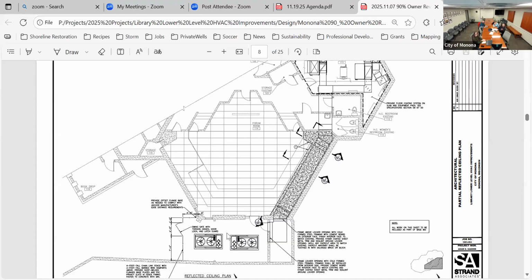And so what we're gonna plan on doing with this design is put occupancy sensors in the rooms so that it can tell the air handler we are occupied at this point in time. So as temps and humidity go up, it can fluctuate what it's doing in the room. So it can cool it more, or try and dehumidify.